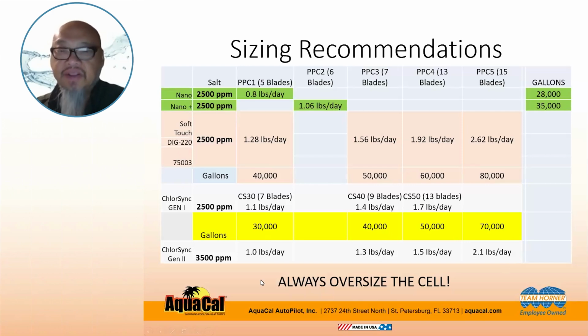All right. And you can see the big marking down here, always oversize the cell. And the main reason I recommend that, it does a couple of things. Naturally, if you oversize the cell, it's going to last longer before you need to replace it. But the other thing with oversizing the cell is, remember I mentioned the sodium hydroxide and the pH rising. One of the nuances with a salt system is that there's a tendency for the cell to get scaled up. And the reason it gets scaled up is because the pH rises with a salt system.